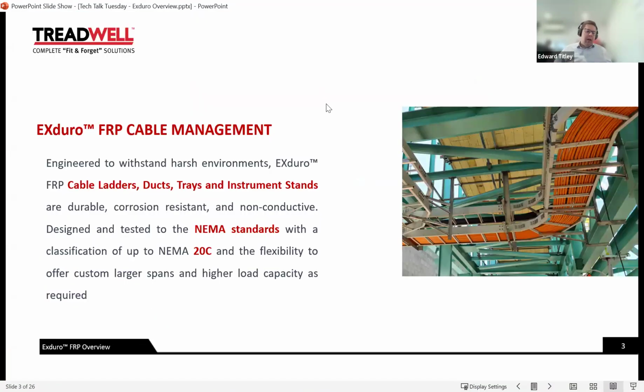So why FRP and cable management? So we started making FRP cable ladder really on client request. Traditionally, in high corrosion areas, stainless was used. Now, there's a couple of challenges that come with stainless, as you would probably know if you work in this sort of corrosion environment. Number one is, as per all metallic products, conductivity, and that can be a challenge or an undesirable attribute with a cable ladder or a cable tray.